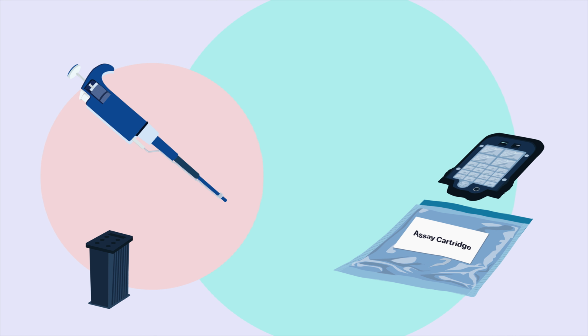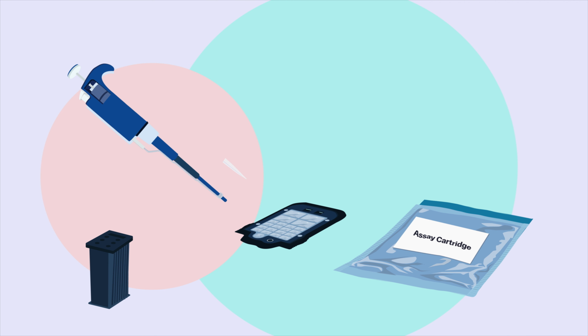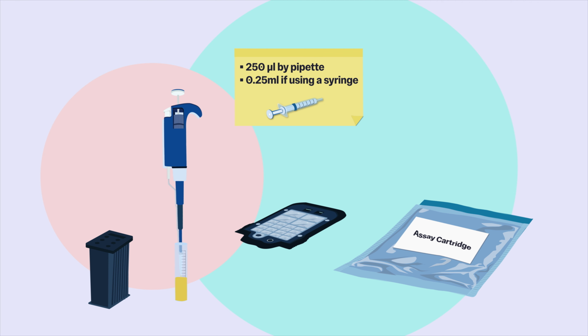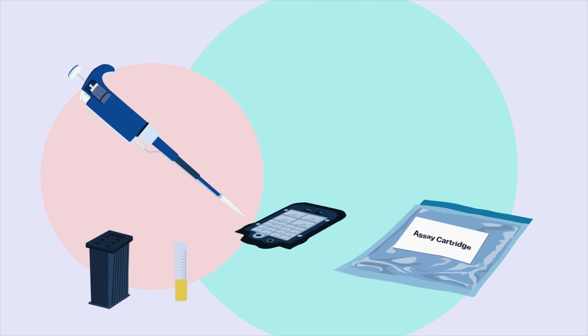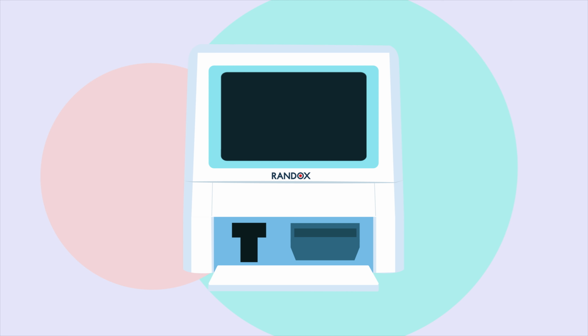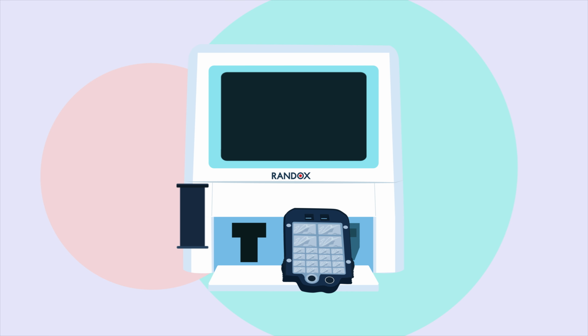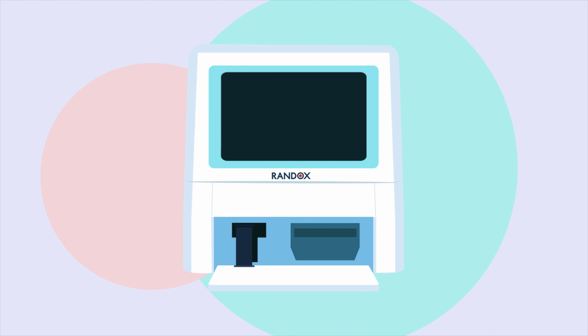Open the foil bag carefully and remove the assay cartridge. Using a pipette tip or syringe, pierce the foil covering the left well. Using a pipette or syringe, transfer 250 microliters of the patient's sample into both the left and the right cartridge wells. Do not dispose of the pipette tip. Place this back in the tip cartridge. Load the assay cartridge into the right-hand drawer and the tip cartridge into the left-hand drawer of the device. Push both drawers into place gently until you hear a click and close the door.